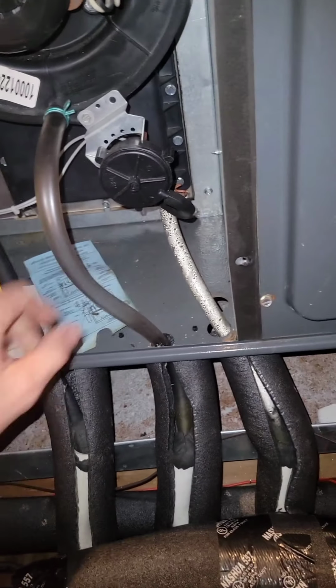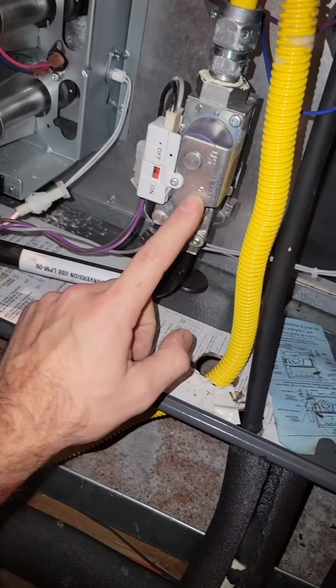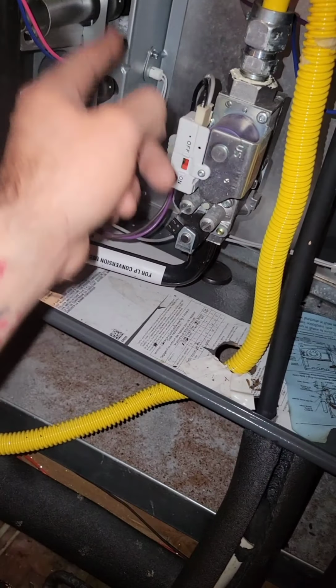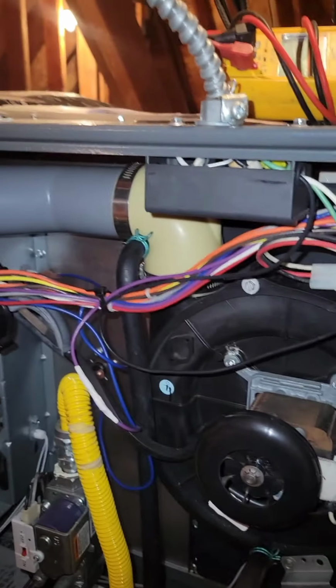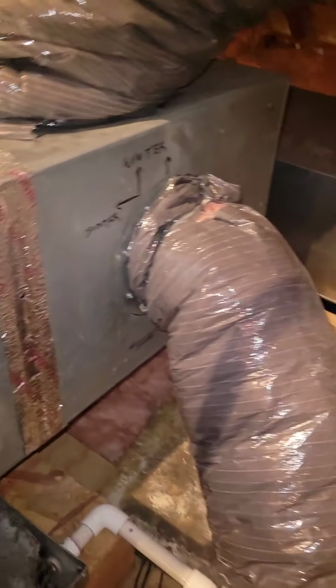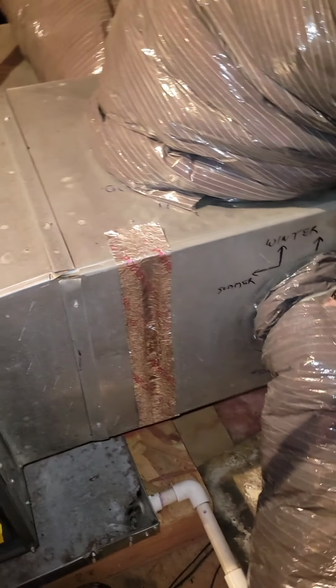And we gotta check again the pressure switches, clean the flame sensor, which is now located on the right hand side, but you can see that this is where the gas valve starts. There's your igniter right there. So we're gonna check all that stuff. And then the filter, how many?